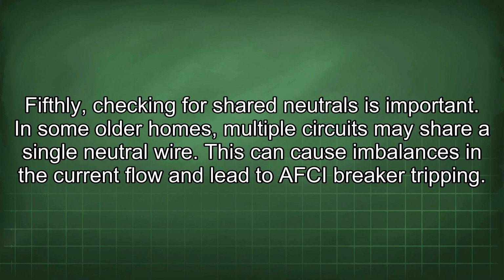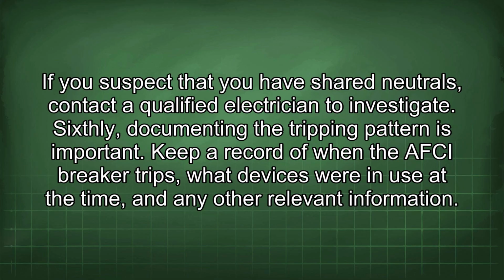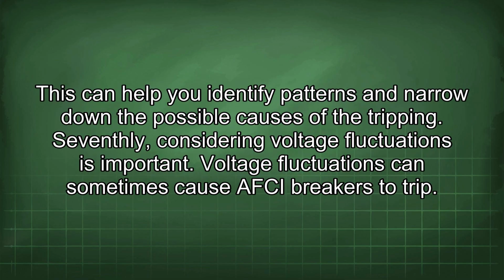Fifthly, checking for shared neutrals is important. In some older homes, multiple circuits may share a single neutral wire. This can cause imbalances in the current flow and lead to AFCI breaker tripping. If you suspect that you have shared neutrals, contact a qualified electrician to investigate. Sixthly, documenting the tripping pattern is important. Keep a record of when the AFCI breaker trips, what devices were in use at the time, and any other relevant information. This can help you identify patterns and narrow down the possible causes of the tripping.